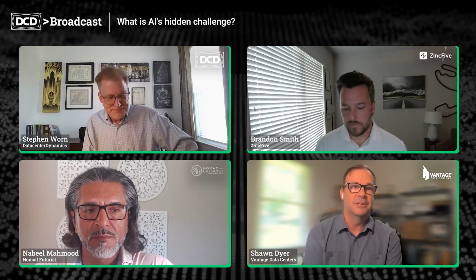No, it's a great segue. It's not new, but the rate of change, the slope we're expanding at, we're hitting a wall. Data centers getting deployed now were designed a year or so ago with infrastructure purchased a year or so ago that could handle about 40 kW a rack, and now it's 100, 150 kW a rack, or they were 4 megawatt data halls, and now customers are asking for 2.5 megawatts per row.